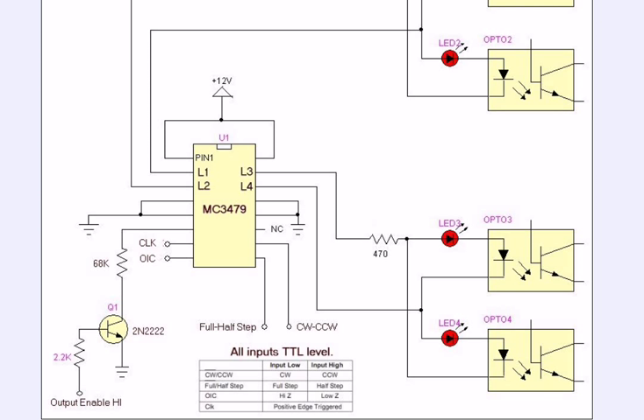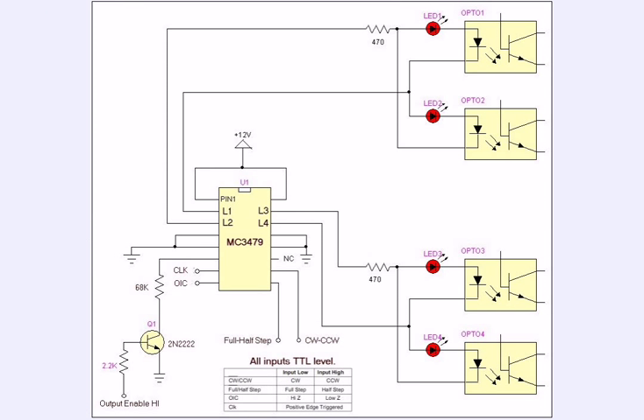Again, looking at our right side of the circuit, we have two sets of optocouplers, and they are wired in pairs back-to-back. So whatever polarity voltage is put out by L1 or L2 or L3 or L4 is going to light up one or the other, or I should say enable one or the other optocouplers, but never both at the same time.